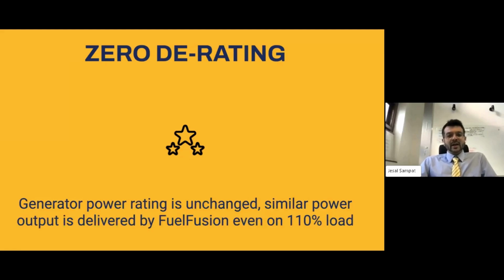There is absolutely no derating. Just as there is zero modification, there is zero derating as well. The generator power rating is unchanged. The same power output is delivered in fuel fusion mode, even at 110% of the load. When the generator is running over and above 100% load, you can achieve the same with fuel fusion mode as well.